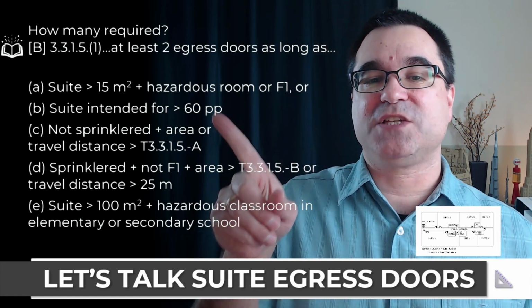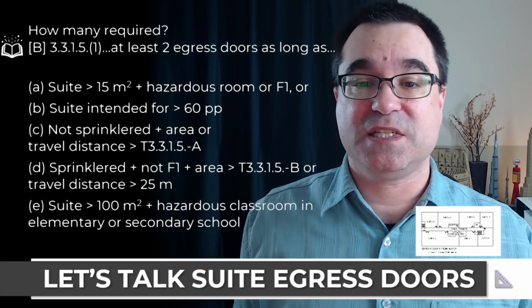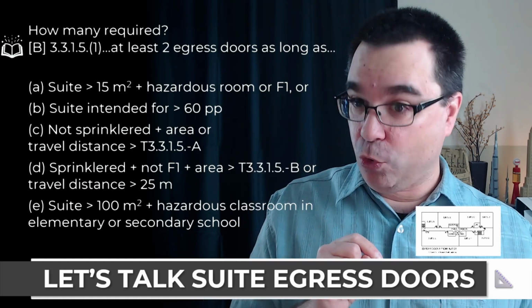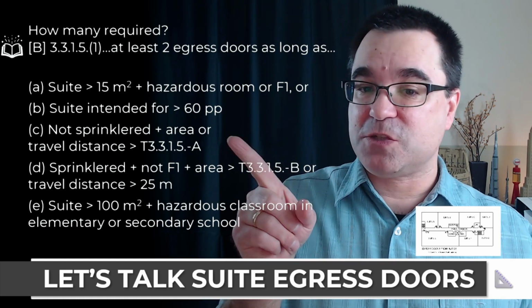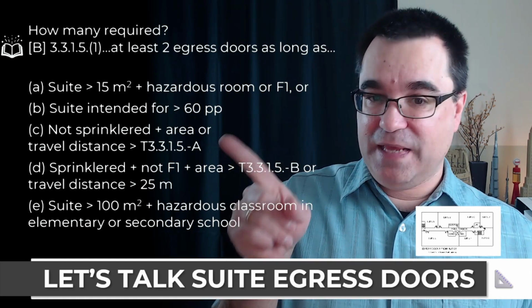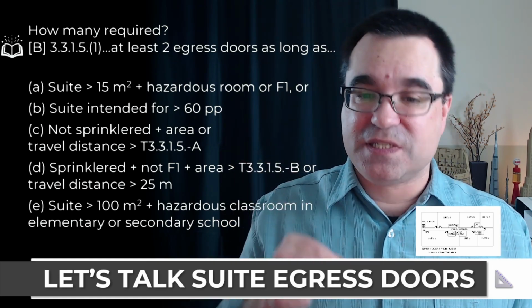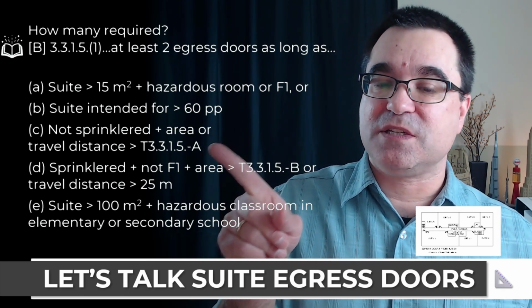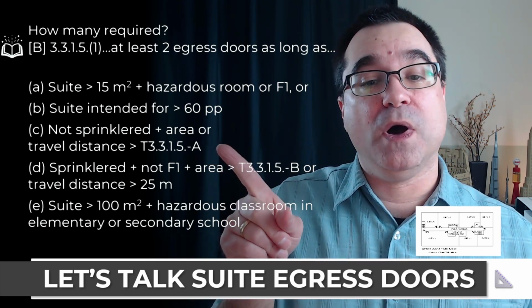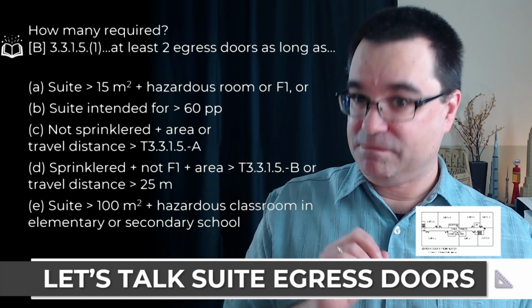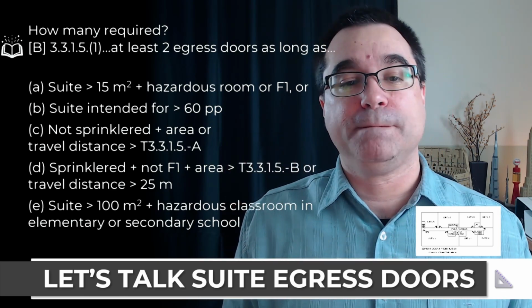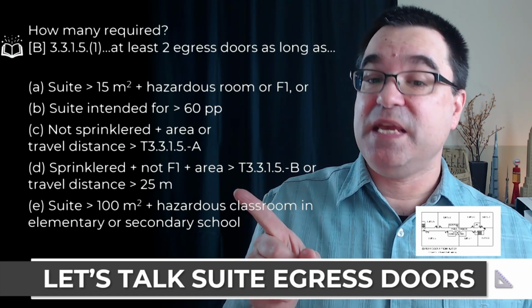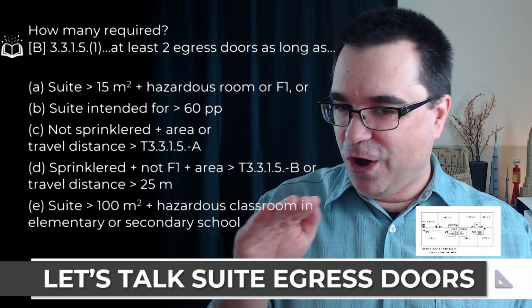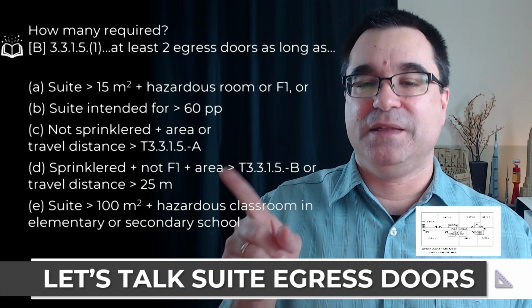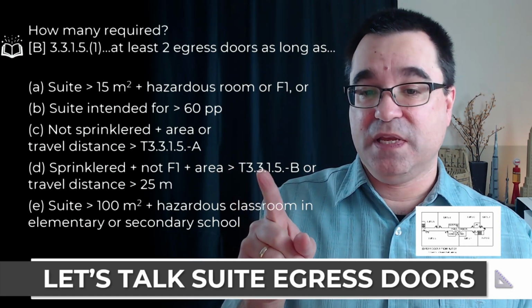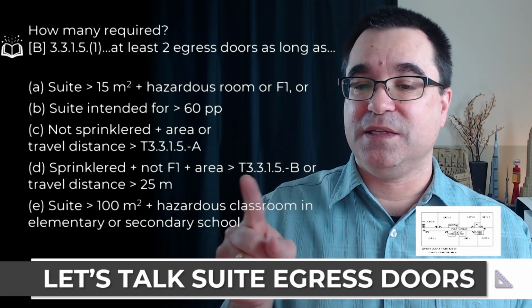So for example, if that suite is intended for more than 60 people, the occupant load of that suite, or if that space is not sprinklered and the area or the travel distance in that space exceeds the requirements of table 3.3.1.5a, then you require at least a second door.